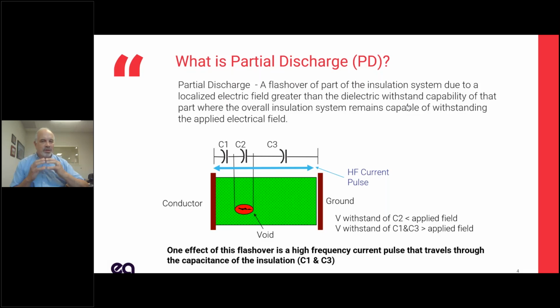What happens is that C2 goes from some voltage to a very low voltage. Let's say we had 3,000 volts across the whole insulation and 1,000 volts on C2. It breaks down and goes to 0 volts. Now I still have 3,000 volts between my conductor and ground, so the voltage at C1 and C3 has to change from 1,000 volts each to 1,500 volts. The way we change the voltage across capacitors, as we all know, is to flow current through it. So it is a high frequency unipolar spike. That current spike creates a number of side effects that we'll talk about, but that's what partial discharge is: a current spike as a result of a flashover.